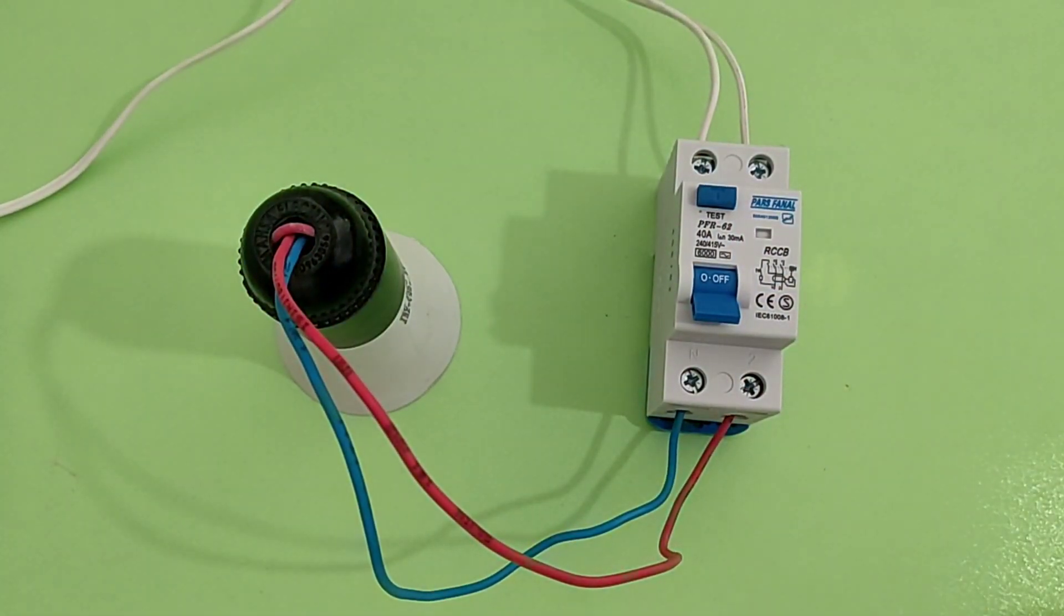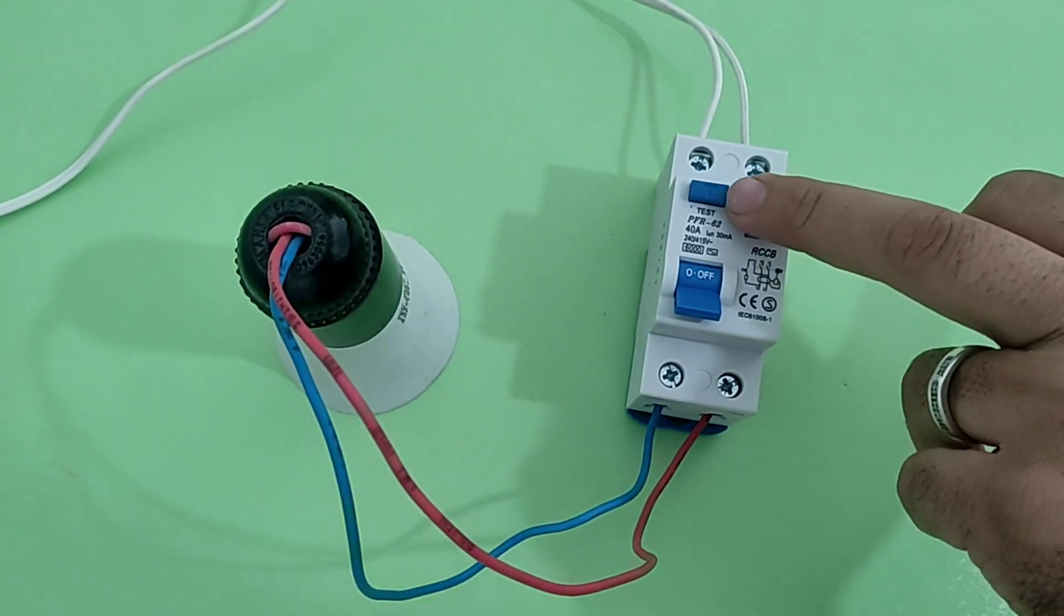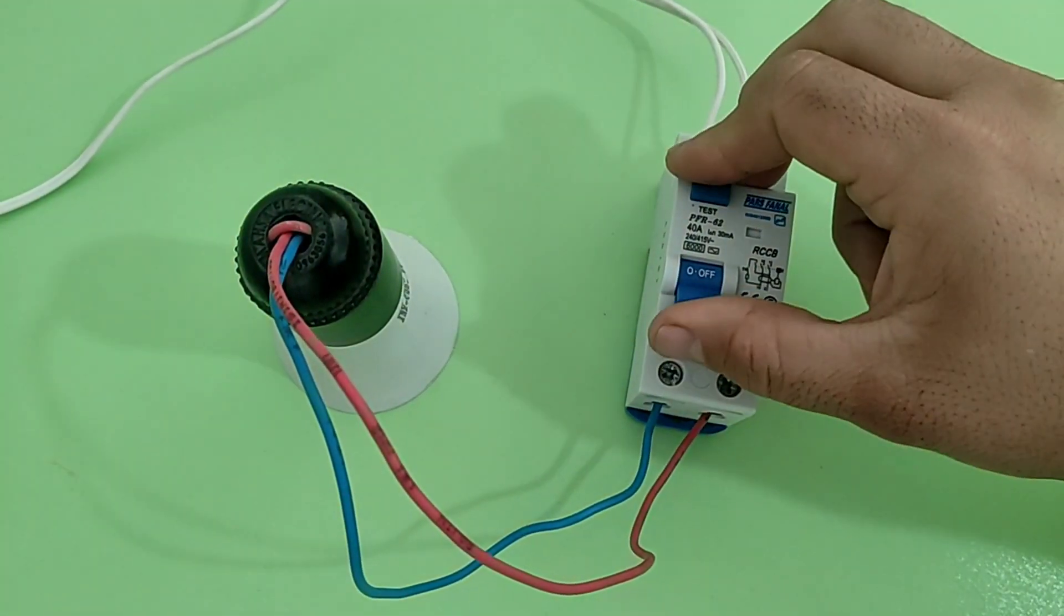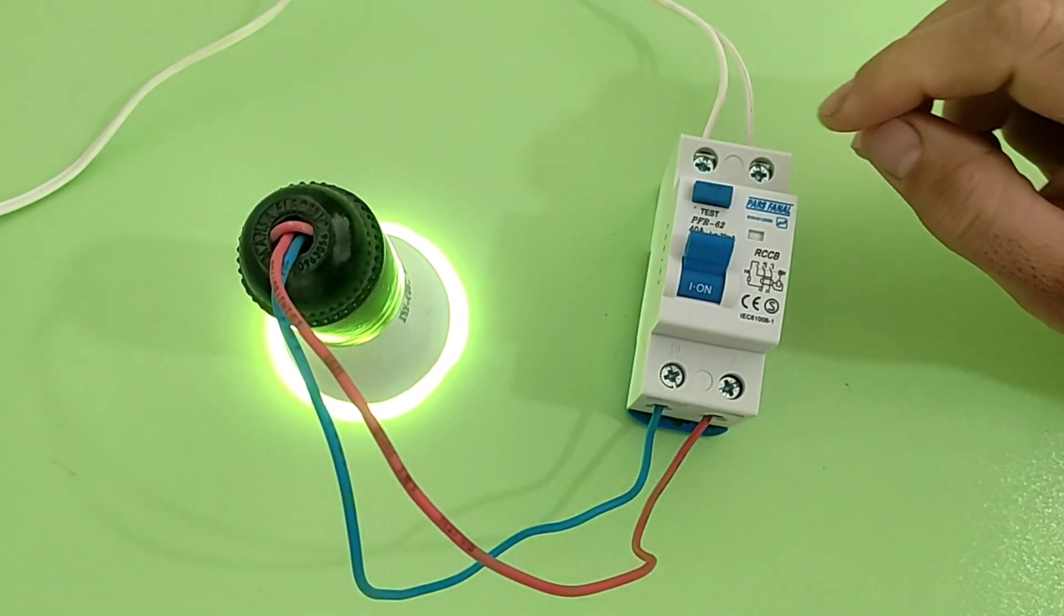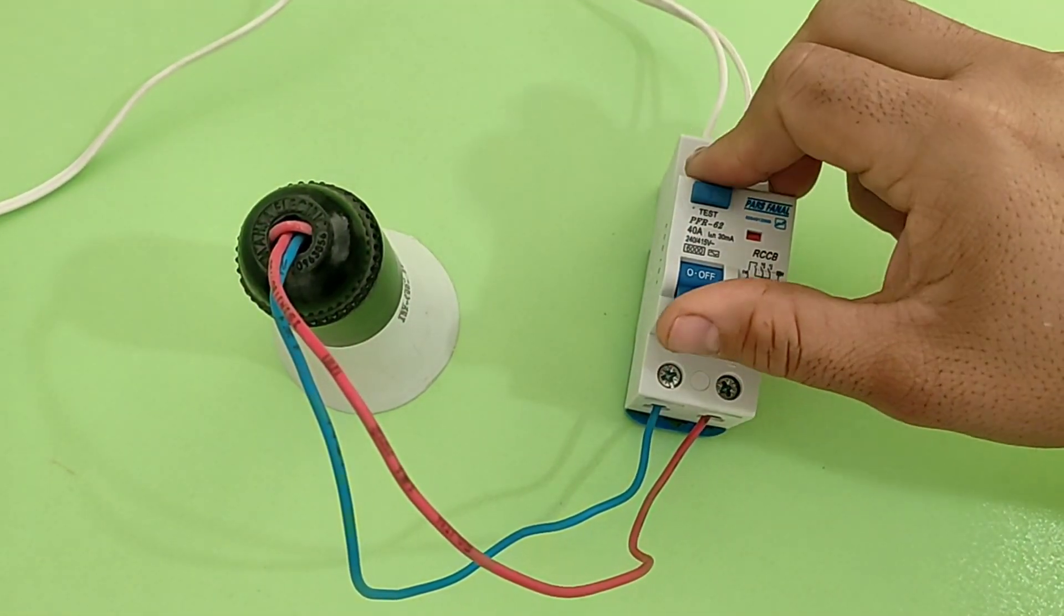For the times when the RCCB switch is connected to the electricity, we can check the health of the RCCB switch by using the test key on the switch. If the switch is healthy, when we press the test key, the switch will be disconnected.